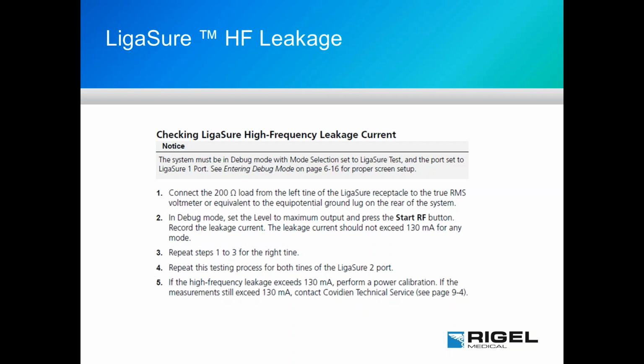And just as we did with everything else, bipolar, we would have to do high frequency leakage testing as well, active electrode by itself, dissipative electrode by itself. And here is the test sequence from their service manual, which talks about how to do the testing with LigaSure. And notice that they set the limits here for 130 milliamps, which is just an example of what I was speaking of a bit earlier, where a manufacturer can choose to test to a lower current value for leakage current, but never a higher current value than 150 milliamps.